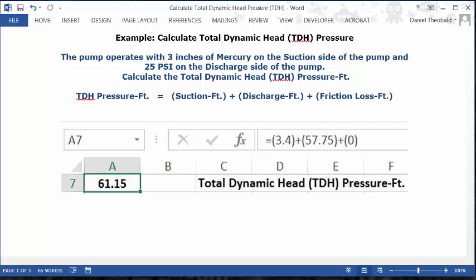Type: equal sign, open parenthesis, 3.4, close parenthesis, plus sign, open parenthesis, 57.75, close parenthesis, plus sign, open parenthesis, 0, close parenthesis. Then press Enter or the Return key. Your answer of 61.15 TDH pressure in feet is your answer.